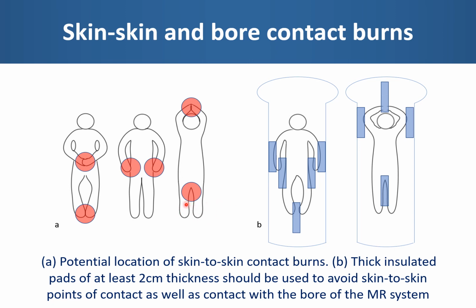Therefore, the manufacturers recommend that thick insulated pads should be used to avoid skin-to-skin points of contact. And in addition, the capacitors within the body coil can also create very strong electric fields, so the patient should also have padding to avoid direct contact between any part of the patient's anatomy and the bore of the MRI system.